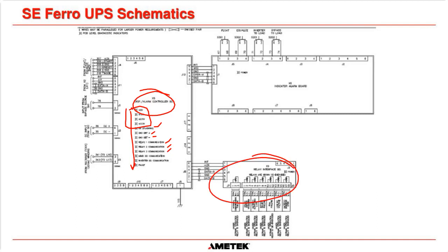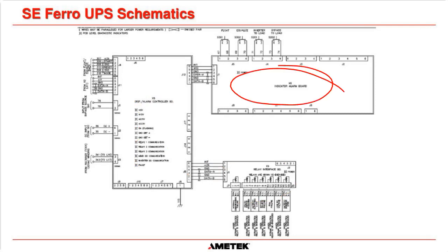So if there was a problem with the communications between this board and this board here, it would give you a red LED saying relay communication fault. And this one here is just a red fault light to tell you if there's anything wrong with this board whatsoever. And then this X5 indicator alarm board, that's basically what deals with the outside world. So the inverter push buttons and all that kind of stuff. That's how you put the system in float, equalize, inverter to load, bypass to load. So that does all the interactions and tells this board here what to do.